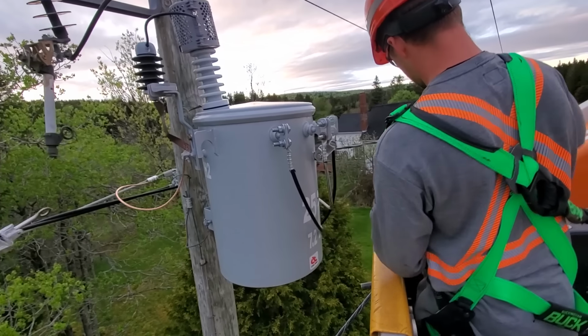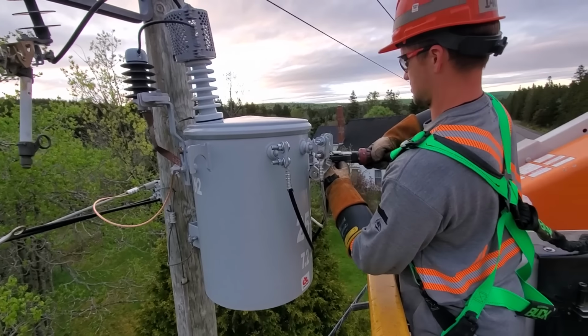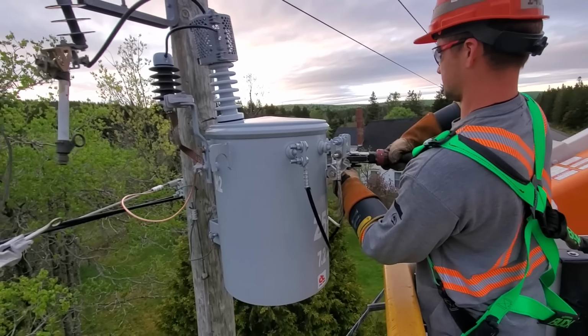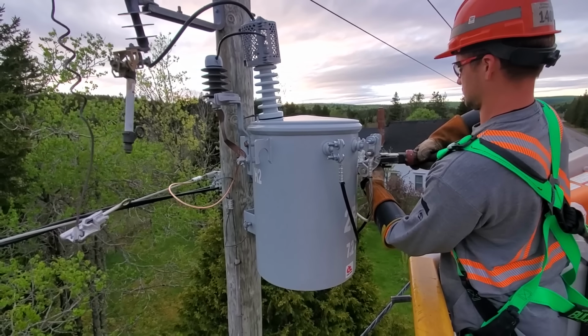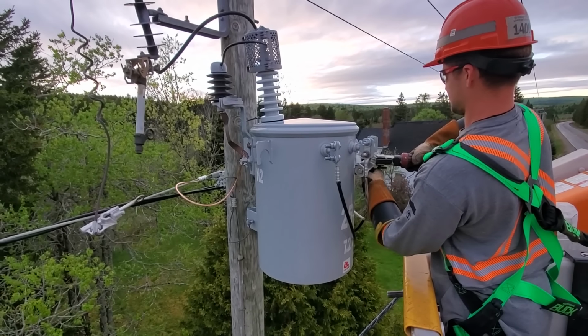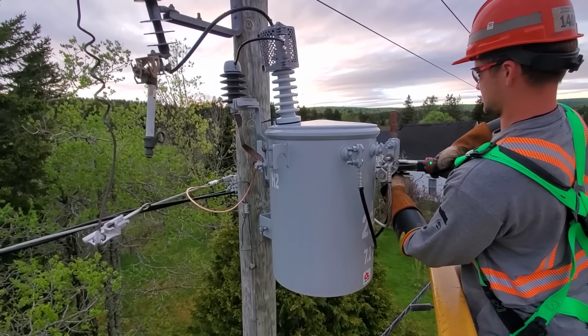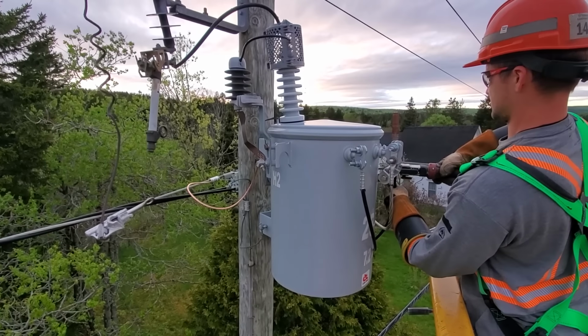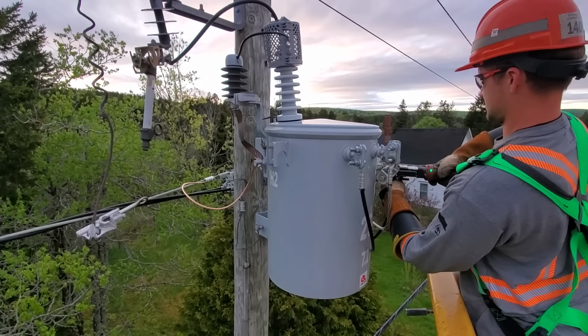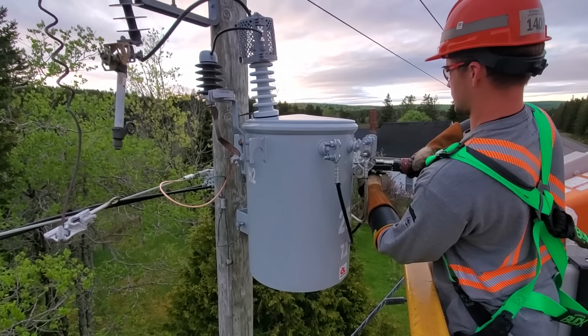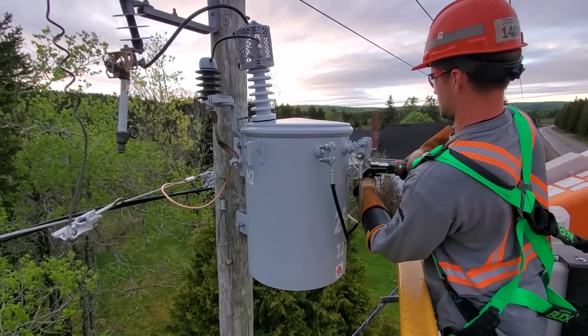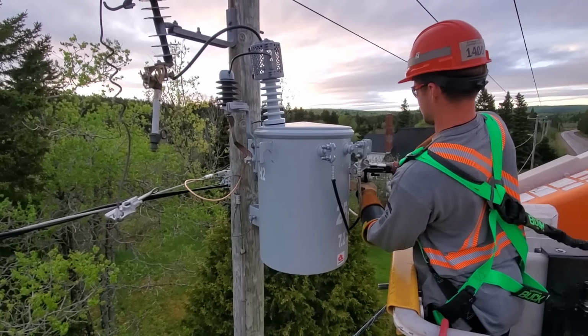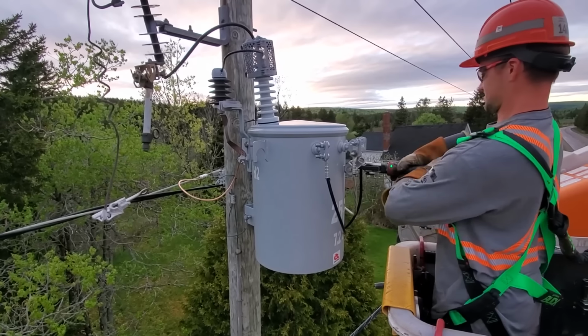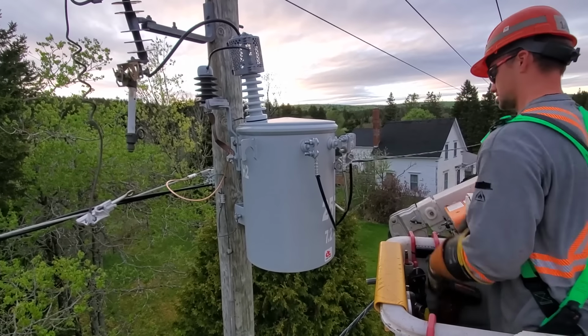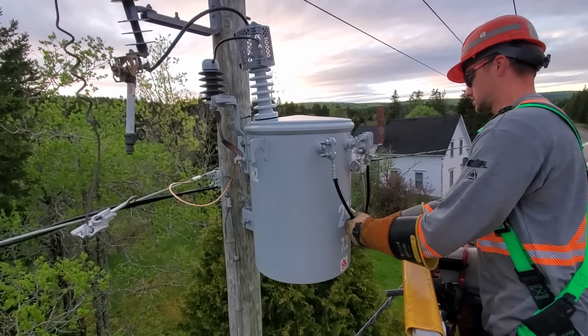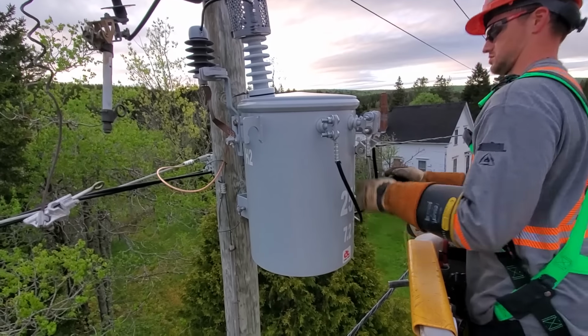That can was pretty old, so I'm pretty confident it was a bad transformer. To tell for sure, we could have disconnected the secondary lines and tried it a third time, but at that point I don't really want to risk actually blowing up the transformer, blowing the top right off. We could have called electromechanics to come out and test the windings of the transformer, but we're so far out of town, it's much easier just to replace it rather than get into testing. It was an old unit, it was due for an upgrade anyways.